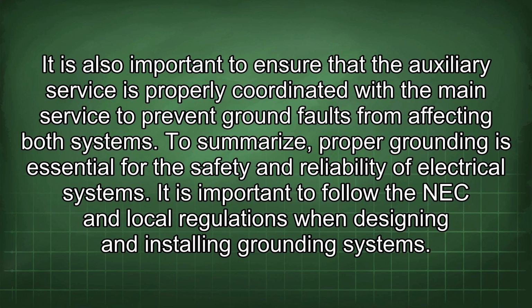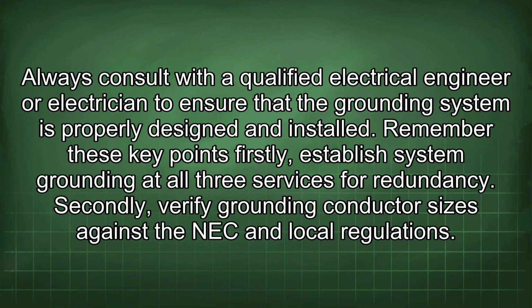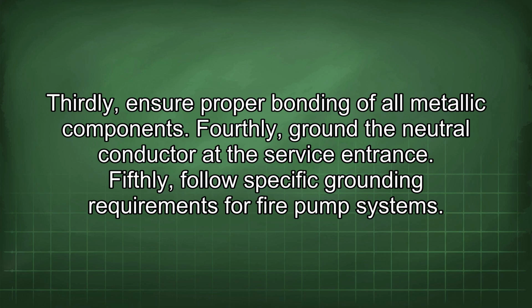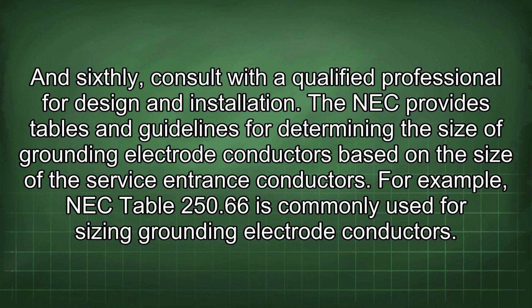To summarize, proper grounding is essential for the safety and reliability of electrical systems. It is important to follow the NEC and local regulations when designing and installing grounding systems. Always consult with a qualified electrical engineer or electrician to ensure that the grounding system is properly designed and installed. Remember these key points. Firstly, establish system grounding at all three services for redundancy. Secondly, verify grounding conductor sizes against the NEC and local regulations. Thirdly, ensure proper bonding of all metallic components. Fourthly, ground the neutral conductor at the service entrance. Fifthly, follow specific grounding requirements for fire pump systems. And sixthly, consult with a qualified professional for design and installation.